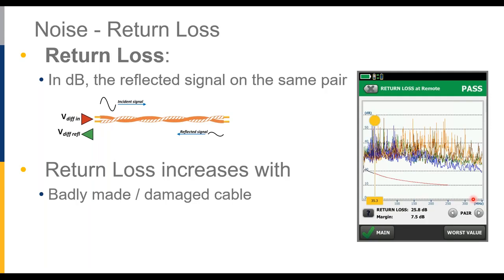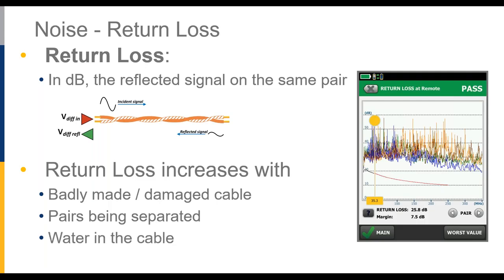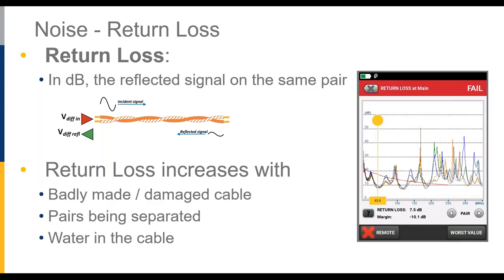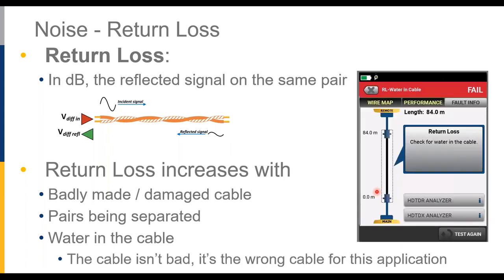Damaged cable can show up clearly in return loss results — you can see where the cable went into modular furniture or was lashed down to the legs of a machine. We want to maintain the physical position of the two conductors in each pair; separating them causes an impedance variation, which causes reflection. Getting water in the cable is a notable industrial case — return loss will look unusual, indicating not necessarily a bad cable but the wrong cable for the application. That's the C in MICE for climatic, or the I for ingress — if you're getting water in, you need a more waterproof jacket.